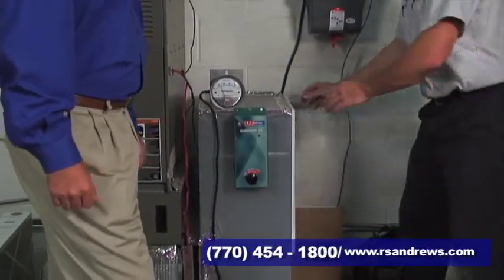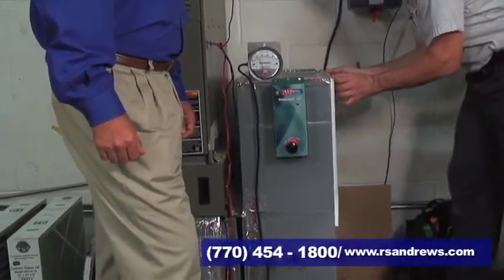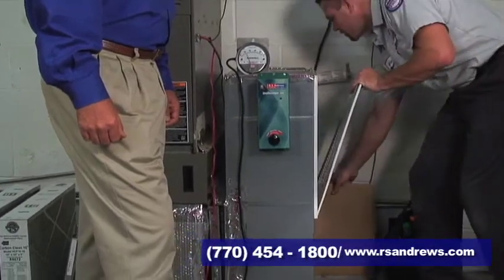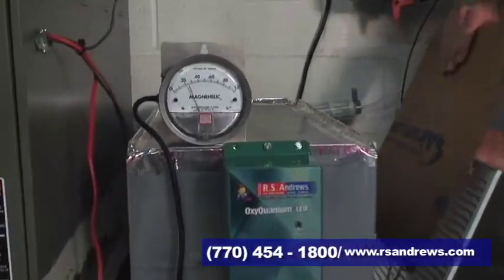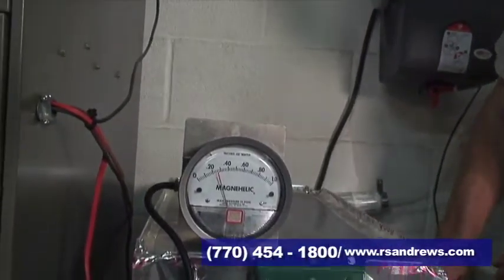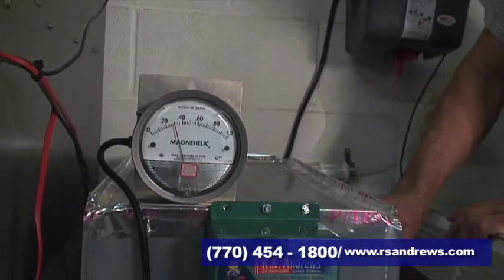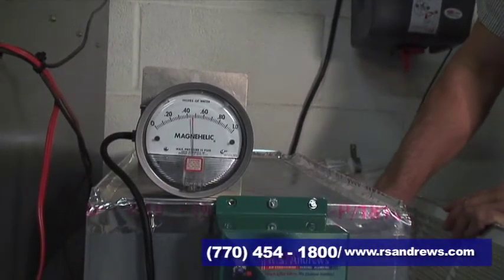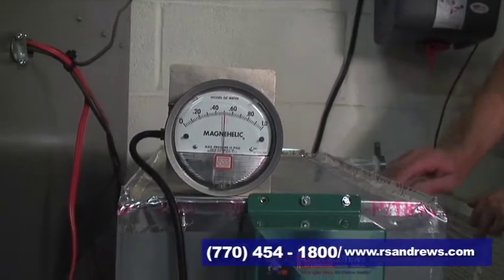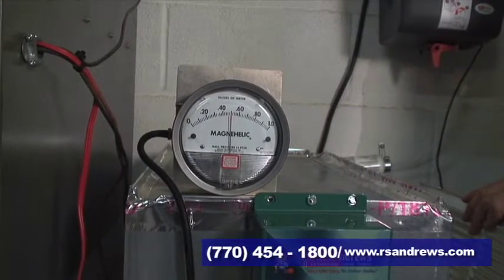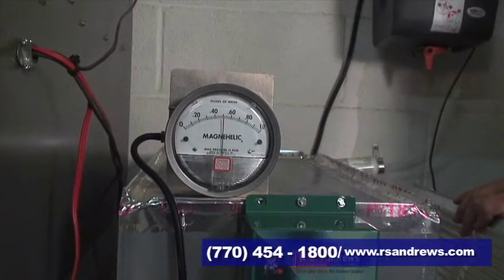Okay. Now this here is the air intake for this system right now. This is, again, either a collapsed ductwork or dirty filters. Now watch that gauge right there. So you can see a dramatic increase on the pressure that is on the motor. And the higher this goes, the harder your system has to work to move air through it.